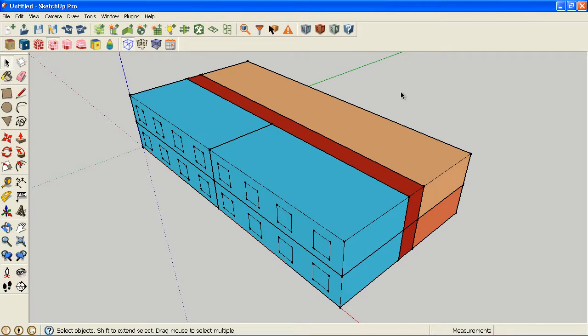So now I've done what I need with the space types. As I assign those space types, I'm changing the number of people that are in those spaces and the schedule those people are in those spaces. So is it all day long? Is it during certain hours of the day? What kind of lighting power density occurs there? What kind of equipment is in there? What kind of outdoor air requirements are needed? So all this is changing just by reassigning space types.